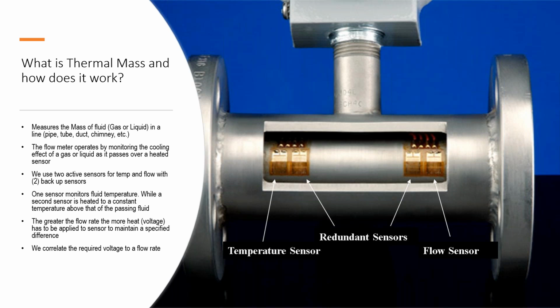So basically at no flow, there isn't much voltage or current needed to keep that sensor maybe 50 degrees above that of the fluid that's sitting in the line. But as flow increases, it's going to require more energy or more voltage to that sensor to maintain that differential, because as fluid comes through, it's going to basically pull heat away from that sensor that's being warmed up. And then we correlate basically that voltage back to a flow rate. And then we output that across a 4 to 20 or several other outputs that we can offer to you.